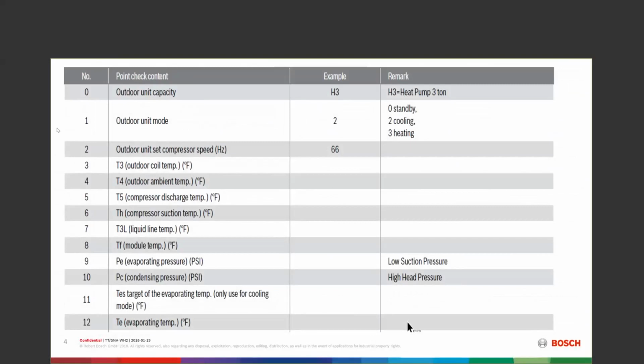So these are the parameters, and let me show you a little bit of the difference between the 1.0 and the 2.0. The 1.0 had the T3. That T3 was my coil temperature. T3 is located on the liquid line about 3 rows up, and it gives me a liquid line temperature number. The only thing you needed on the 1.0 to get subcooling readings was a liquid line thermistor clamp-type thermometer. Today on the 2.0, you do not need that anymore because we have number 7. Number 7 is the T3L. The T3L is located right behind the service valve on the liquid line, and it allows me to see that liquid line temperature.